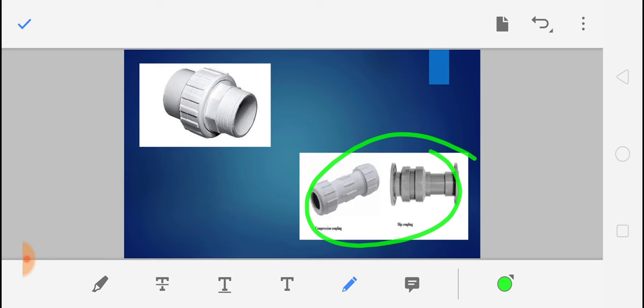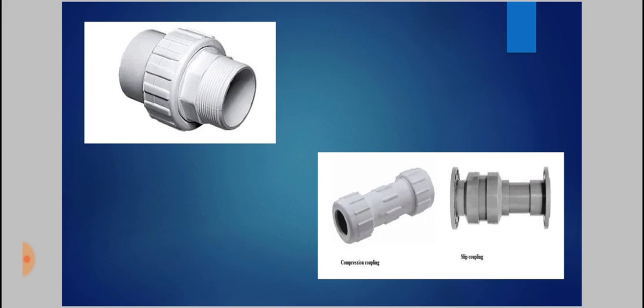The next fitting is the union. A union is a type of fitting that functions similarly to a coupling, but unlike a coupling — which cannot be removed after fixing — a union can be removed wherever needed. One end of the union is threaded and another end is free; it consists of a nut, male end, and female end with threading. Unions are also useful for pipe maintenance purposes. This covers the main types of pipe fittings and completes the third module. Thank you.